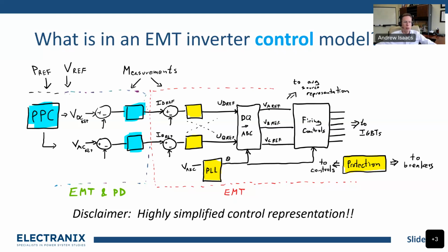So now you can say, okay, you ordered an active power. You can compare the currents measured right at the inverter terminals and control those currents very tightly to give you the internal voltage reference that you want. So now we're on this path here, so that you get the currents out of the IGBTs. You're going to go through to firing controls and actually fire some IGBTs in your model, or maybe you have an average source representation. But in order to do that, you need to have a phase lock loop down here coming in, and that's going to also go to your firing controls.